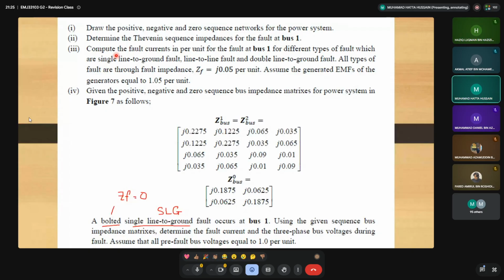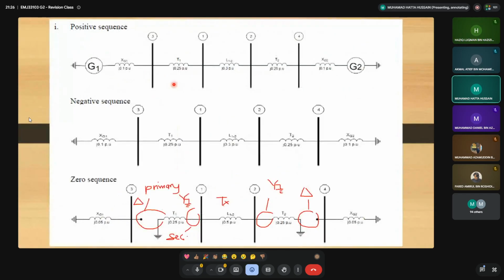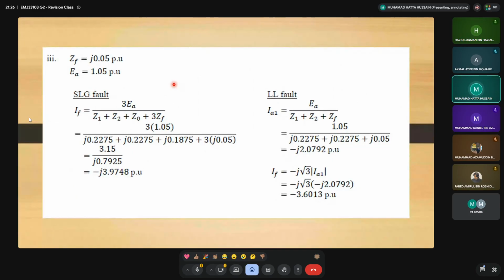You compute the fault current in per unit for the fault at bus 1 for different types of fault, which are single line to ground fault, line to line fault, and double line to ground fault. Which means that it covers all the 3 types of the unsymmetrical fault. And all types of the fault have fault impedance equal to J0.05 per unit. Assume that the electromotive force of the generators equals 1.05 per unit, which means that you need to know the formula. Without the formula, you cannot solve this question.